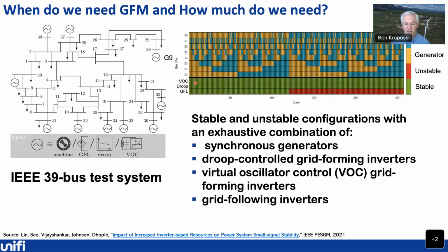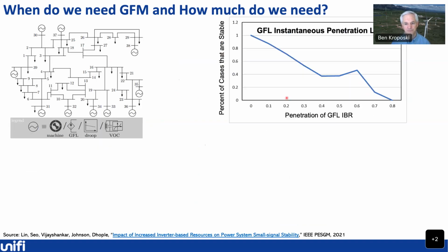The key piece that this shows you is the fact that these grid forming inverter controls, virtual oscillator control or the droop control, all the cases were stable when they looked at those technology deployment. Whereas on grid following, roughly about half the cases were unstable. And so let's take a closer look at those unstable cases and where they were appearing in the system. So if you take again that particular one, the 39 bus IEEE system, and you look at this graph here, this is showing you penetration levels of grid following inverters, from 0 to 80%, and then the percentages of cases that are stable.